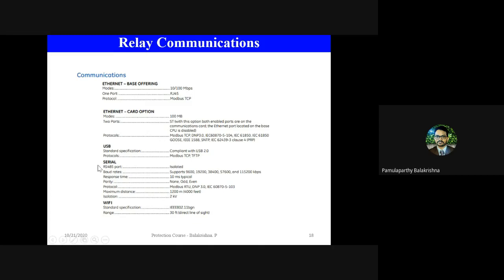It can also support USB communication. You can just plug a USB cable into the relay and start communicating with it. In places where Ethernet is not possible, again specifically in remote and rural areas, you have to go with serial based communications. Serial based communications are nothing but you lay a dedicated cable between the device you want to communicate with and the remote control center. These cables will communicate in a serial manner with the corresponding host devices present in the substation.